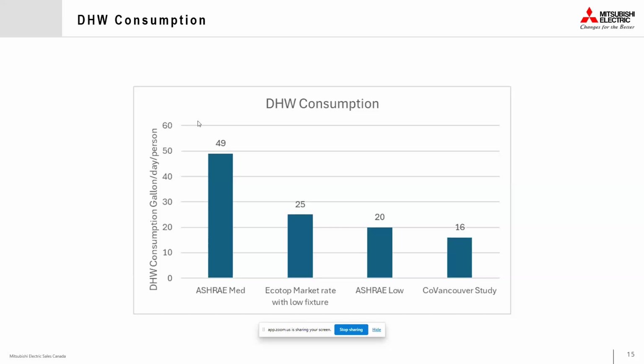There's one more reference that comes from a City of Vancouver study recently done for different types of buildings. That's the actual consumption of those buildings, and they say it could be as low as 16 gallons per day per person. So those are different criteria. You have to find which type of building you have, how much is the occupancy, what's the type of fixture, and all this together, and find the best possible number for your design.